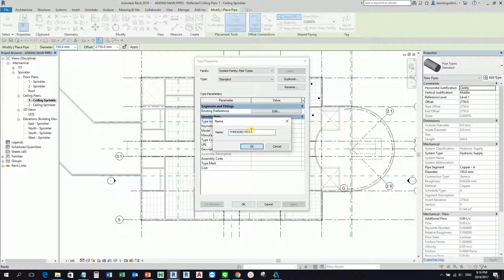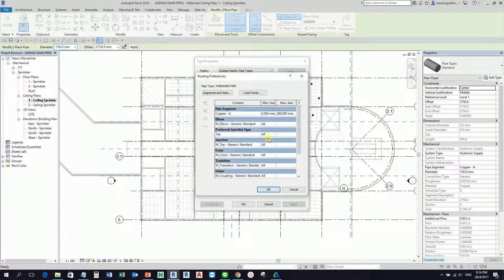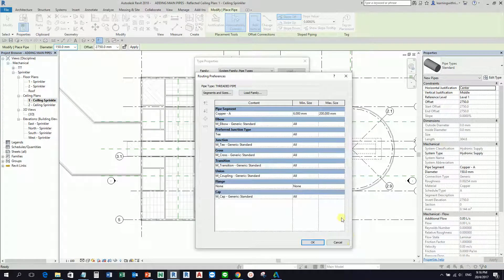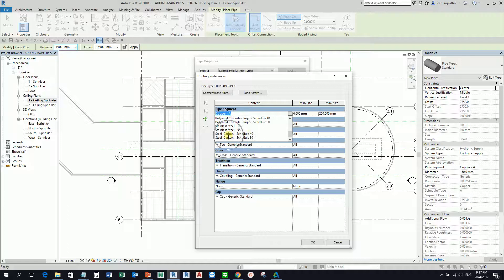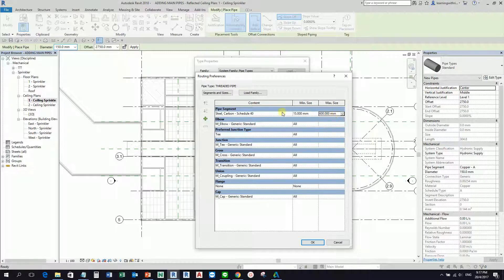After creating that type, from Segments and Fittings I'll select Edit for my routing preferences. By selecting this you can see the default contents for your pipe segment, elbow, etc. for your pipe type. I'm going to edit this — for the pipe segment instead of Copper A I'll use Carbon Steel Schedule 40. For the minimum size it's 15mm, and I'll increase the maximum to 600mm, so that's the range of my pipe.